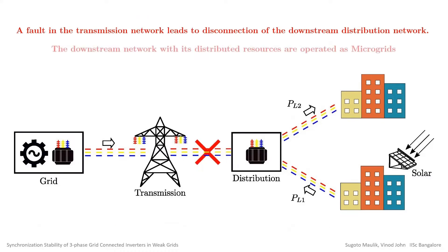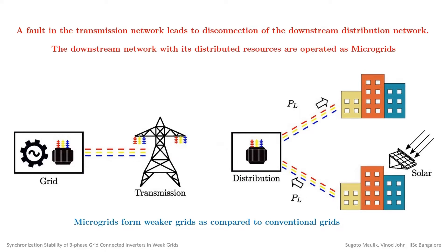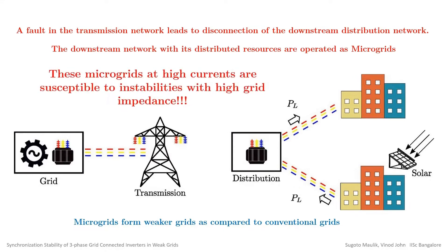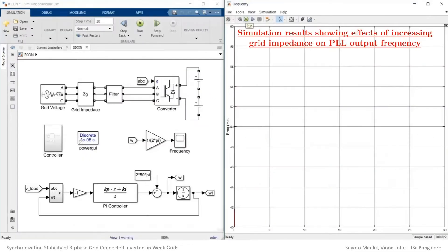These distributed resources have the advantage of being operated as microgrids when disconnected from the main grid due to a fault. However, these microgrids form weaker grids owing to their higher grid impedance and thus are susceptible to instabilities at high grid currents.